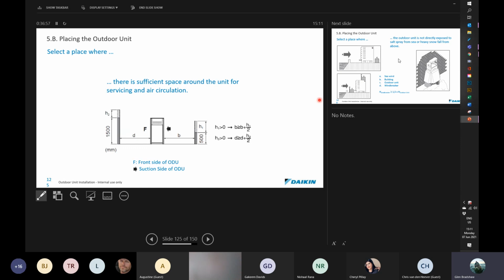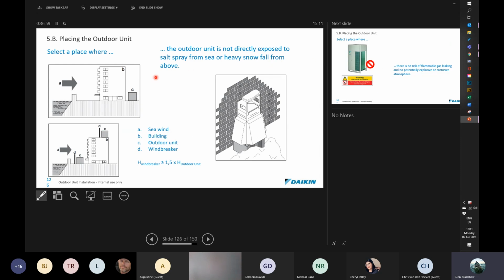Something along the coast, which is very important, is to be aware that salt air will find its way into anything if you're very, very close to the sea. A is depicting the sea wind. We have a building and an outdoor unit. If we place the outdoor unit on the front of the building, we need to create a windbreak to try and drive out some of the salt so we don't get direct salt air. If it was placed on the roof, we would also need to put a windbreak on there to try and protect the unit, and the better place would be to put it behind the building, and allow the building to be the windbreak.